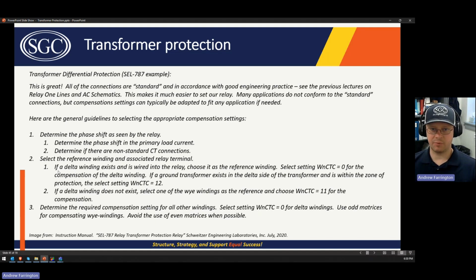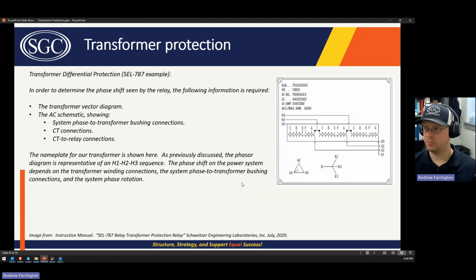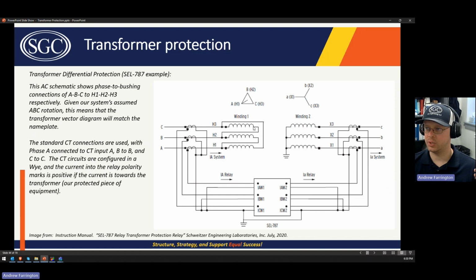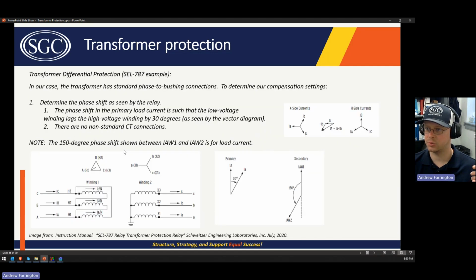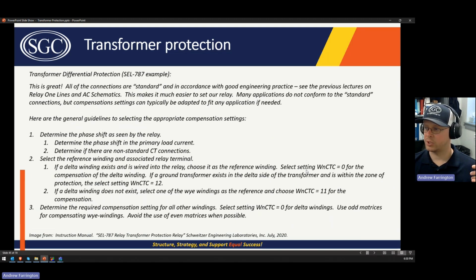So this is from the SEL 787 instruction book. And it says, if a delta winding exists and is wired into the relay, choose it as the reference winding. And we do have that, right? Relay winding 1 is connected to winding 1 of the transformer, which is our delta connection. So we're going to use that as our reference winding. And then we're going to select the setting of WN. This is our winding 1, so it'll be W1CTC equals 0 for the compensation of the delta winding. And if a grounding transformer exists in the delta side of the transformer and is within the zone of protection, select the setting of winding 1 CTC equals 12. So this is based on the clock position, like we talked about. 0 and 12 are kind of used interchangeably because they're both vertical from the origin.